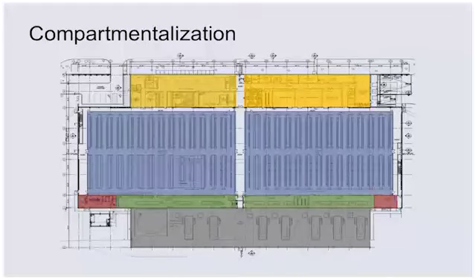Compartmentalization: we designed the facility so it would be compartmentalized in the event of a fault or smoke occurring. We contain that fault to one data hall, but it also allowed us to turn up the facility earlier. By having this compartmentalized solution, we turned up the first data hall three months ahead of data hall B, so while construction continued in Suite B, we were deploying servers and getting our network up and running.